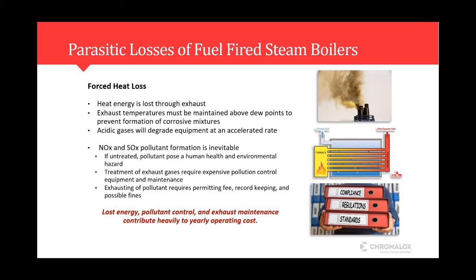And it's also important to know that it's almost a necessary evil, because you have to keep your flue temperatures above the dew point, because the last thing you want is that temperature to drop, and then all those harmful gases that are being emitted start to condense and turn into more acidic condensation that can actually wreak havoc on the system itself. So again, I call it a necessary evil, where you almost have to send some of that heat out to the flue to make sure that that temperature is above dew point.